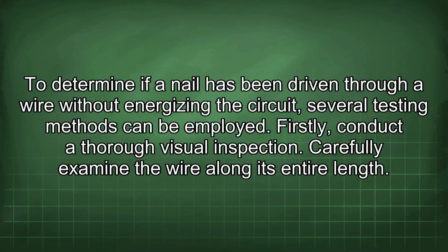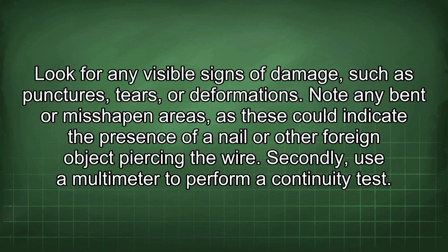To determine if a nail has been driven through a wire without energizing the circuit, several testing methods can be employed. Firstly, conduct a thorough visual inspection. Carefully examine the wire along its entire length. Look for any visible signs of damage, such as punctures, tears, or deformations. Note any bent or misshapen areas, as these could indicate the presence of a nail or other foreign object piercing the wire.